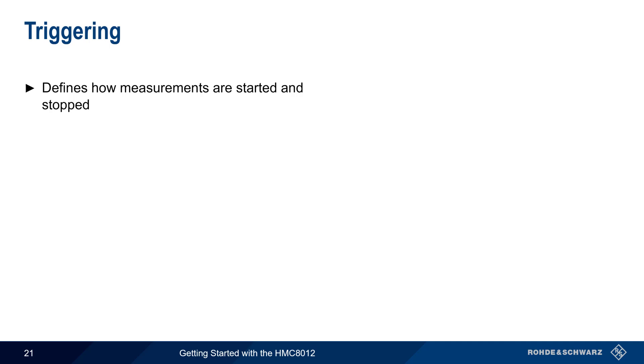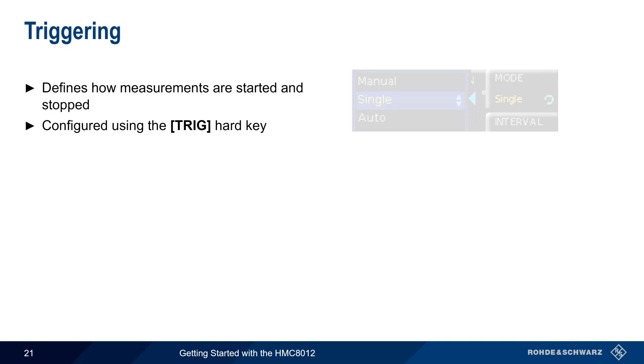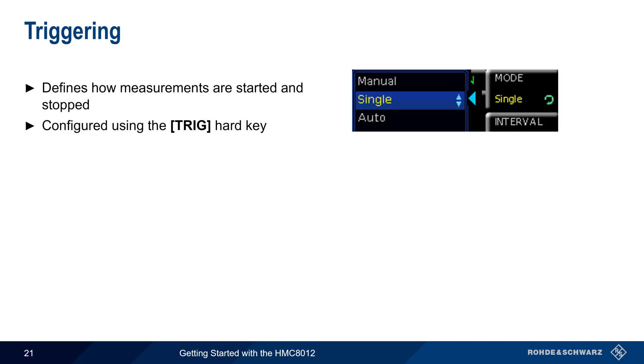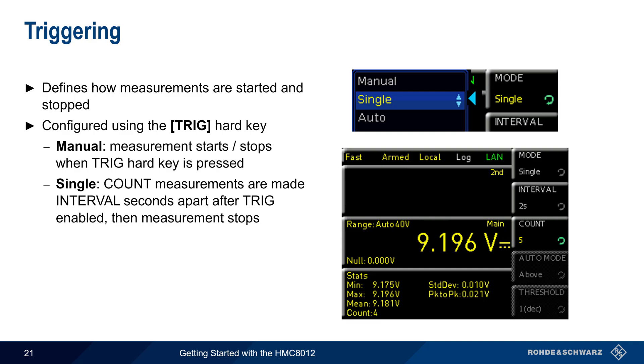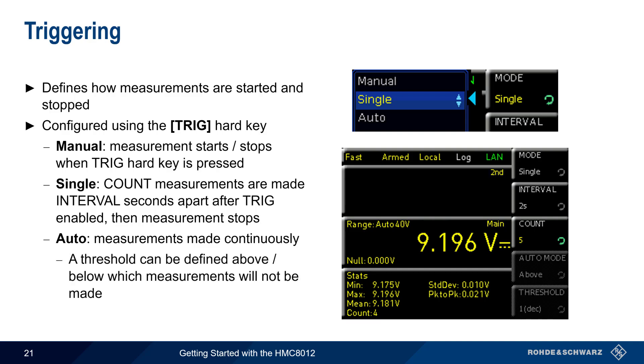Triggering defines how measurements are started and stopped, and the trigger types and parameters are configured using the trigger hard key. There are three trigger modes: manual, single, and auto. In manual mode, measurements are started and stopped by pressing the trigger hard key. In single mode, the user defines a count – the number of measurements to make – and an interval, which is how far apart these measurements are in time. The default mode is auto, in which measurements are made continuously, though this mode allows a threshold to be defined above or below which measurements will not be made.